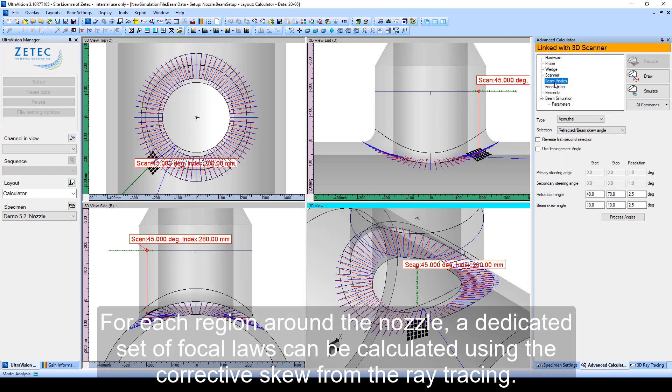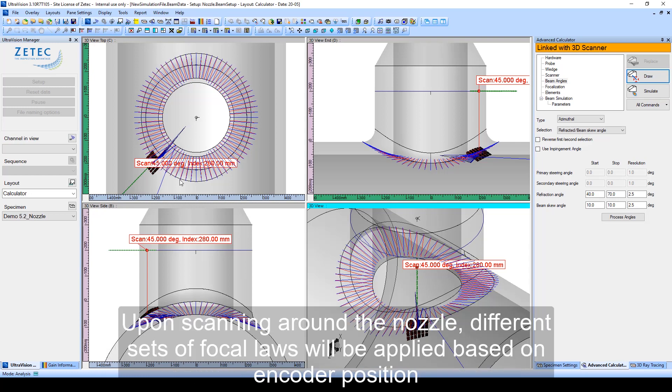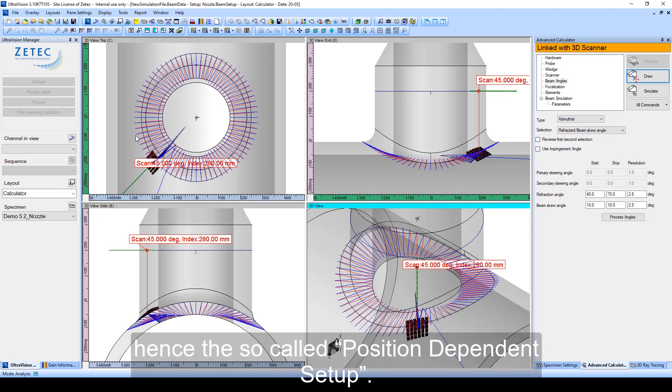For each region around the nozzle, a dedicated set of focal laws can be calculated using the corrective skew from the ray tracing. Upon scanning around the nozzle, different sets of focal laws will be applied based on encoder position, hence the so-called position-dependent focal laws.